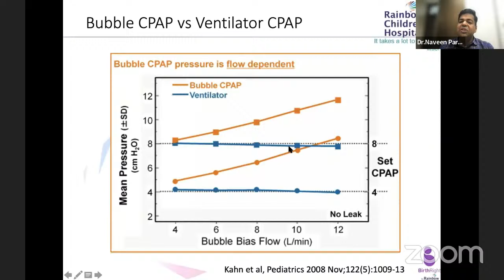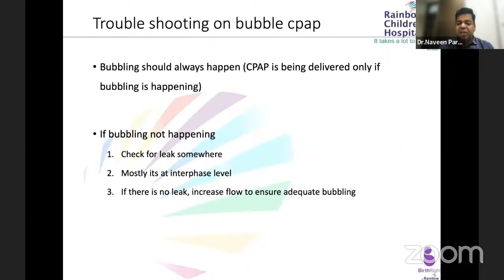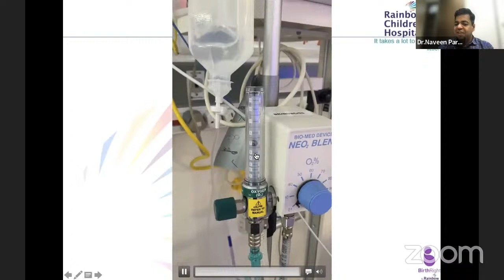So, troubleshooting: bubbling should always happen. CPAP is being delivered only if bubbling is happening. If bubbling is not happening, check for a leak somewhere. Mostly it's at the interface level. If there is no leak, then increase flow to ensure adequate bubbling. Like, let's look at this. This is the continuous bubbling, and the flow is 7 liters, right? So bubbling is adequate, no change needed.